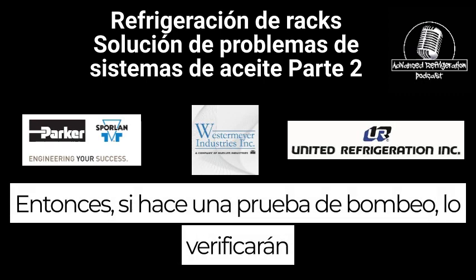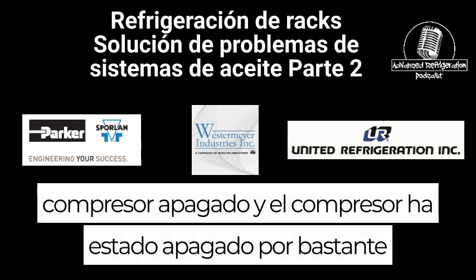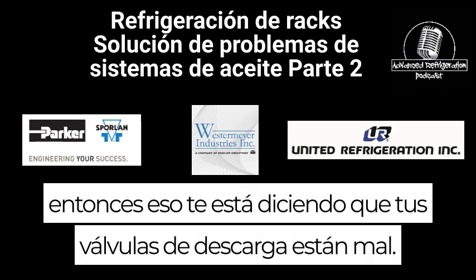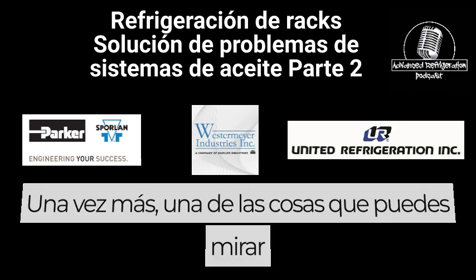So if you do a pump down test, that'll check to make sure that your suction valves are holding. If you have the compressor off and the compressor has been off for quite a while, but the discharge line is still smoking hot, then that's telling you that your discharge valves are bad, in fact shoving discharge back into your crankcase once again.